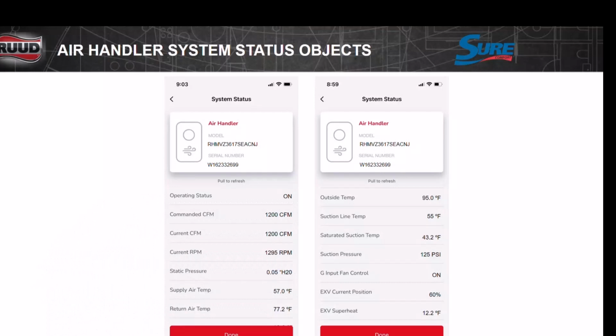That's a problem. If you ever see that, it means you're running high static, because the maximum RPM of that motor is 1295, and we never want to see it hit max. When it hits max, it hits a limiter, and that limiter backs it back down. Then it goes back up, and then back down. What that's going to cause is the motor to go out prematurely.